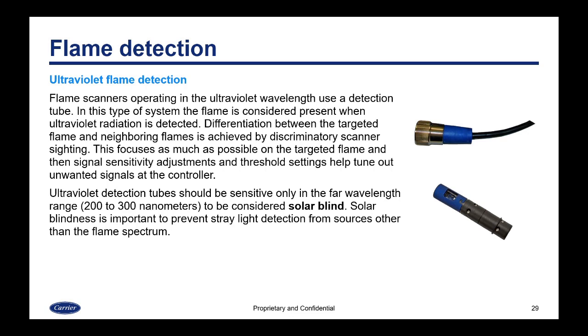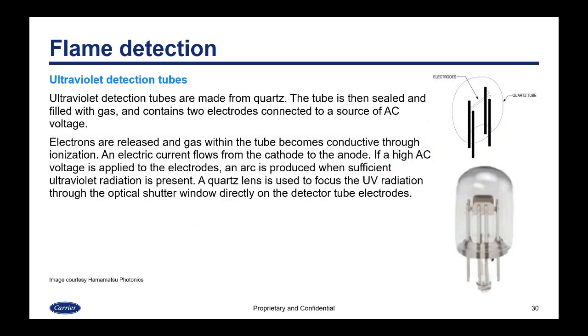Ultraviolet detection tubes should be sensitive only in the far wavelength range of 200 to 300 nanometers to be considered solar blind. Solar blindness is important to prevent stray light detection from sources other than the flame spectrum. Ultraviolet detection tubes are made from quartz, sealed and filled with gas, and contain two electrodes connected to a source of AC voltage. Electrons are released and the gas within the tube becomes conductive through ionization. An electric current flows from the cathode to the anode, and if a high AC voltage is applied to the electrodes, an arc is produced only when sufficient ultraviolet radiation is present.